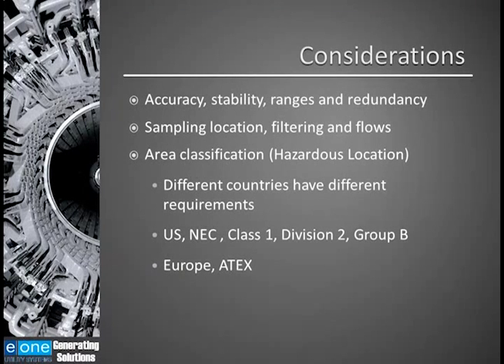I mentioned earlier about the area classification. Because they're bringing hydrogen to the sensor, the area that they're used in becomes a hazardous location. So you want this equipment certified to be used in those hazardous locations. Different countries have different requirements. In the U.S., it's the National Electrical Code, Class 1, Division 2, Group B. In Europe, it's ATEX. Then other countries have different requirements.